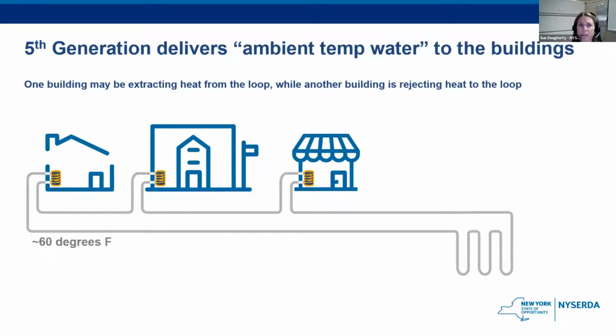Another example is a fifth generation heat pump system, an ambient loop design where the network of piping distributes lower temperature water, closer to 60 degrees Fahrenheit. Instead of the heat or chilled water being produced centrally and then distributed, the ambient temperature water is distributed to the buildings, and a heat pump inside each building can produce hot or chilled water and distribute that.